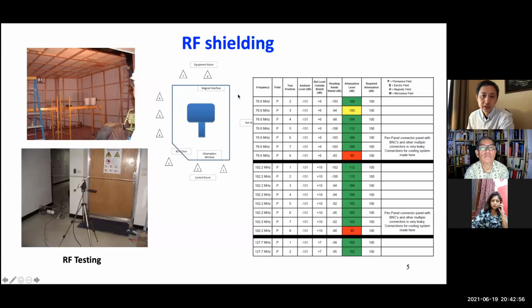So this is a drawing of a scanner room. You can see the spots 1, 2, 3, 4, 5. Those are the locations that are tested. And then after that, we will receive a report. Usually, this testing is done by the manufacturer, but physicists need to be present to make sure they do the right thing and that the result is either within criteria or it's not. If not, then we need to make sure they are corrected.